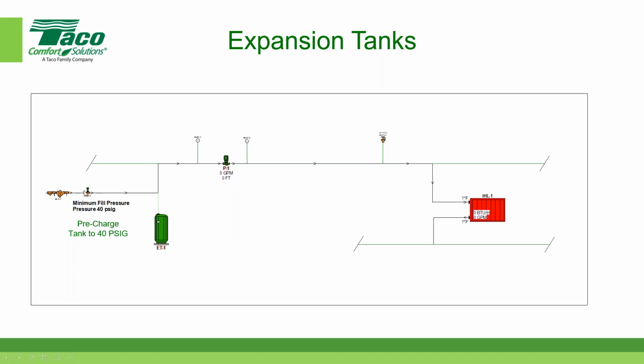So here's the pressure regulating valve over here, and this is the water connection to the city main over here. That's also the pre-charge pressure. That means that when I pre-charge this tank, the tank comes from the factory pre-charged on the air side to only 12 pounds. But in order for it to operate properly in the system, before I connect the expansion tank to the system, I have to pre-charge the air to the minimum or fill pressure of the system. We just calculated the minimum pressure. I have to increase the pressure in the air side of the expansion tank until it gets to 40 pounds. Once it gets to 40 pounds, I can then connect it to the piping system.